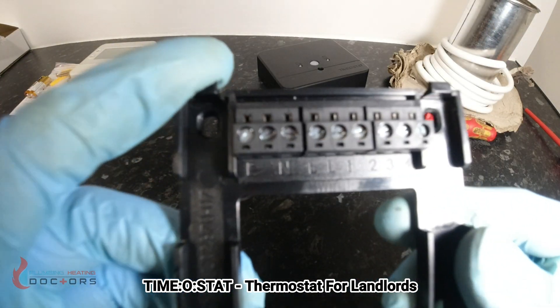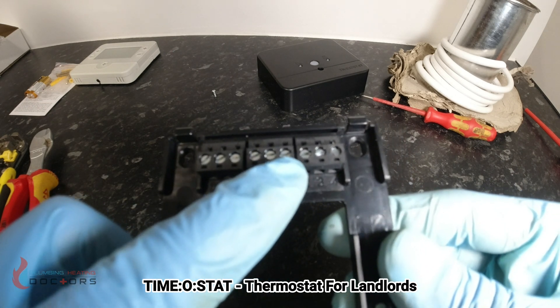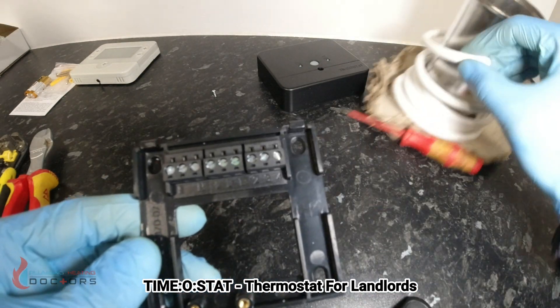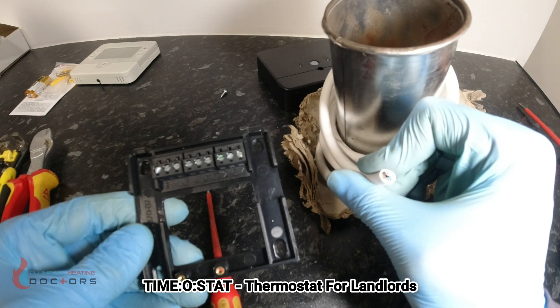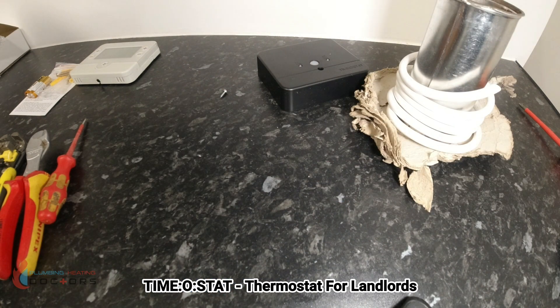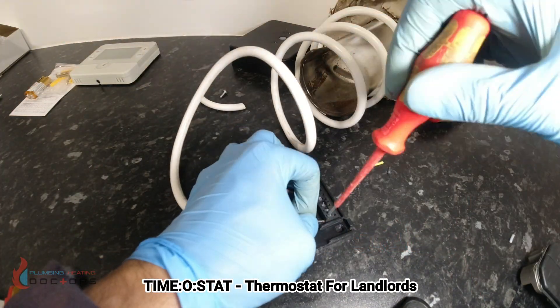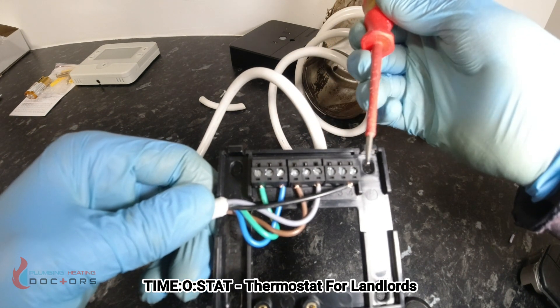Inside the receiver, you have earth, neutral, and live. All you need to worry about is number one, which is common, and number four, which is the switch from the boiler. I'm going to be using five-core flex cable 0.75 — you can get a reel of this from Toolstation, which is normally the cheapest place. As you can see, you've got earth, neutral, live, your common, and then your switch back to the boiler.